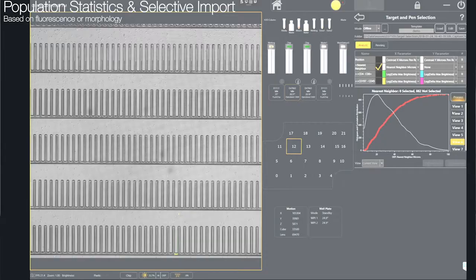You can see all the cells—green are those that fall within the gate, red are the doublets that we want to avoid. Then we can activate a predefined gate that is basically CD8 positive, CD4 negative, shown here. If we click on any cell either on the image or in the FACS plot, it'll highlight the exact cell in the data and also where it is on the chip. Then you can verify all the images and make sure that the machine is identifying the cells you want.